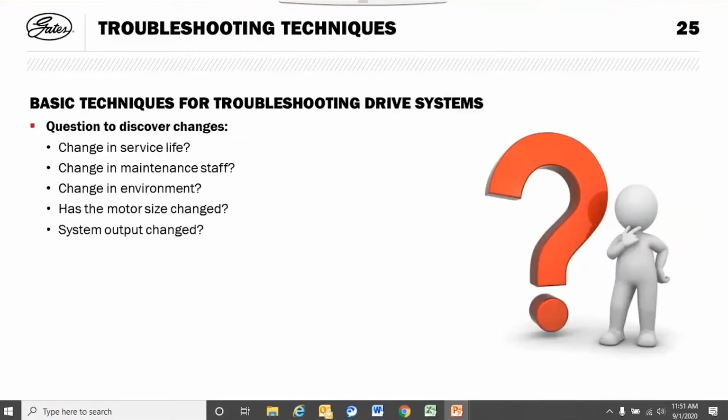Maintenance staff, if they're trained, sort of like what we're doing here. We have other PowerPoints and stuff we can go in to help train the people at whatever location you end up going to on proper installation. Is it the right size motor, the right size sheaves? You might have too small of a sheave for the motor that you have. And a belt always has a minimum size that it wants to go around on a pulley.